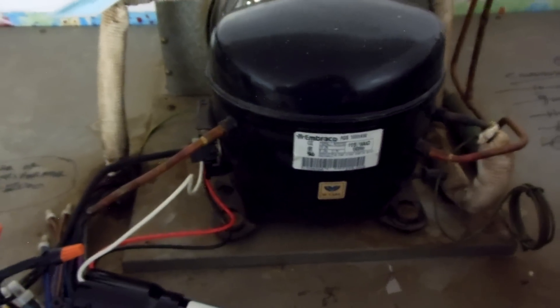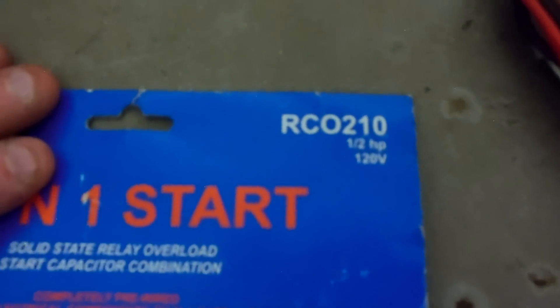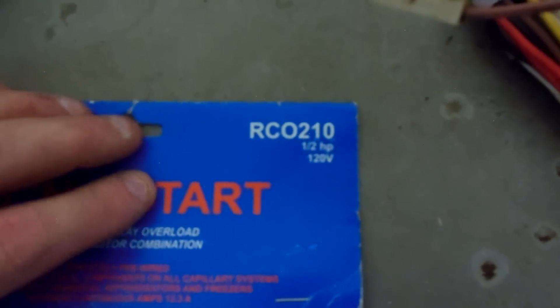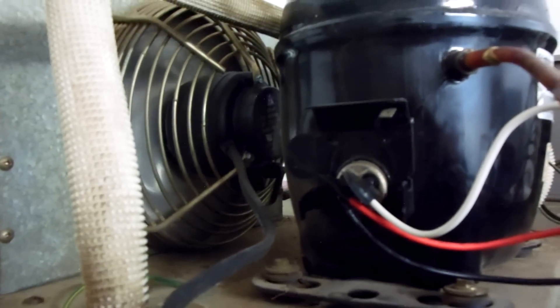The start components went kablooey on this compressor so it wasn't starting - it would only start like every sixth time. What you can use is the RCO210 kit. The RCO410s are good for a half-horse, but I use the RCO210 on everything including this unit, which the Embraco tag says is a third-horsepower but is the size of a half-horse compressor. The RCO210 works awesome as a three-in-one hard start kit.